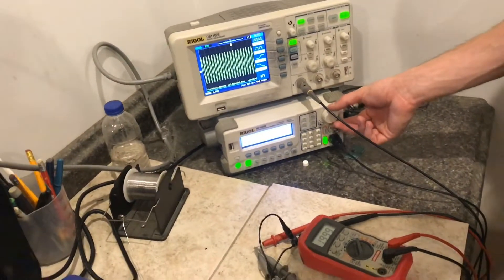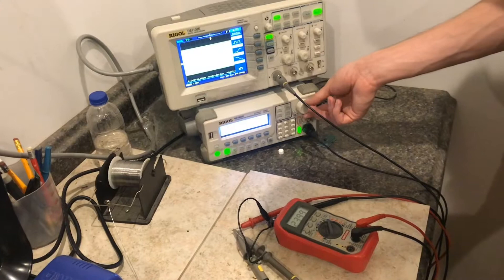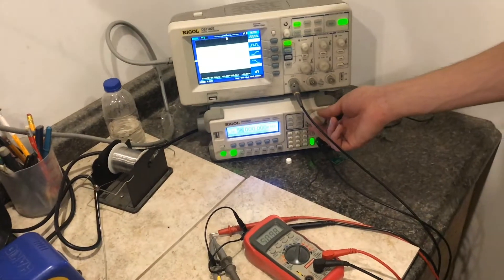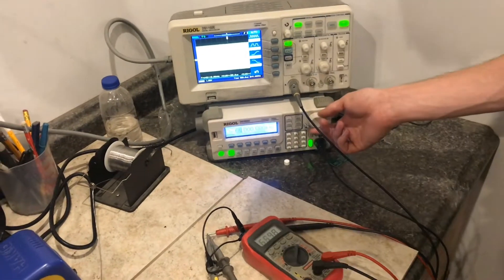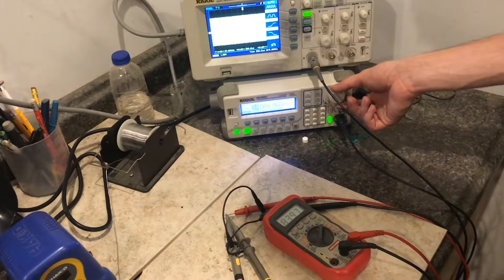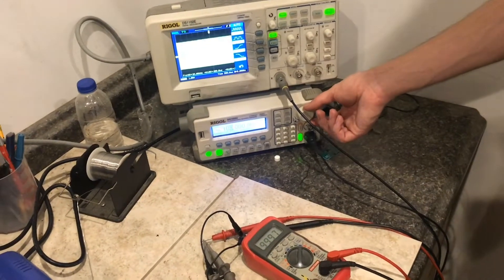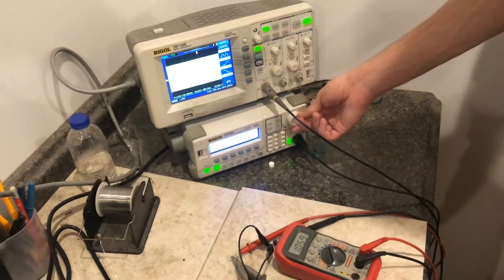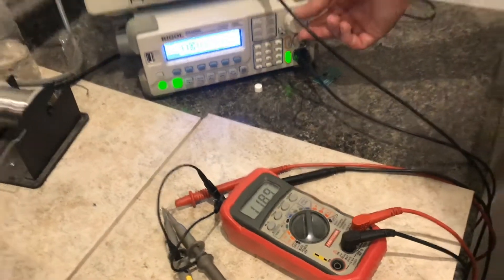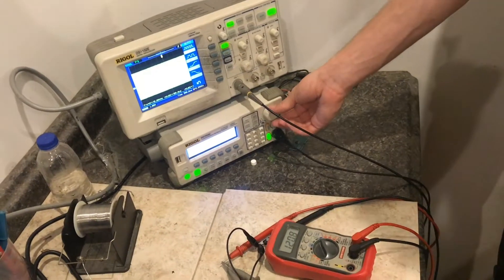Sure, well let's test it. Sine wave, we're going to take this up until it doesn't go anymore. 5, 10, 15, 20, 25, 35, 40 kilohertz. 50, 60, let me slow down, make sure it's still 67, 66.98. Okay, 83.97, still pretty good. 100, 100 kilohertz, we're at 0.3 percent error. This is actually allowing me to measure a frequency higher than the Fluke did. We've lost a digit of precision now in order to make room for the 100th place.